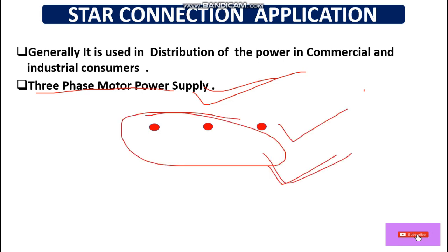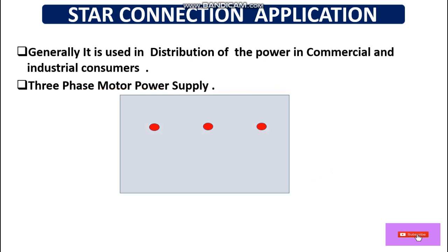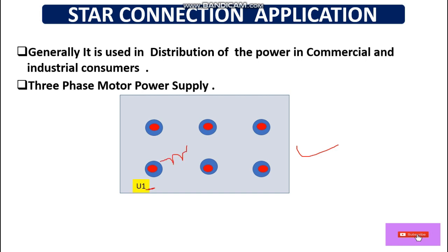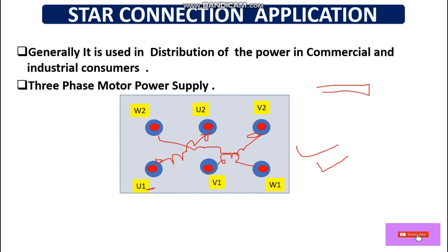Another important application is three-phase motor power supply, which is the basis of the star-delta starter. A three-phase motor terminal box always has six terminals: U1, U2, V1, V2, W1, W2. Internally the coils are terminated in a criss-cross pattern at the terminal block, with one end of each coil on one side and the other end on the other side.